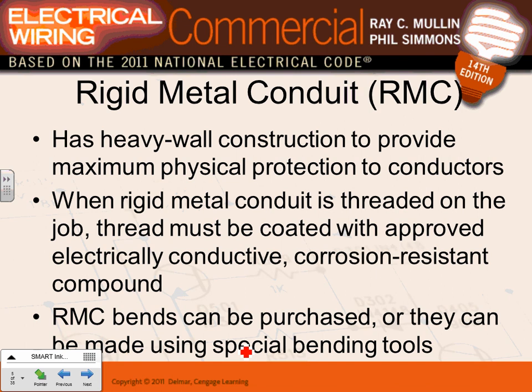Typical applications: bringing service above ground into a building, hazardous locations, and manufacturing floors with overhead cranes moving around. Anything where you could run a vehicle into the conduit - use rigid. Does that make sense? Rigid provides maximum physical protection. It's not just physical protection like every conduit - it's maximum physical protection with heavy-wall construction.